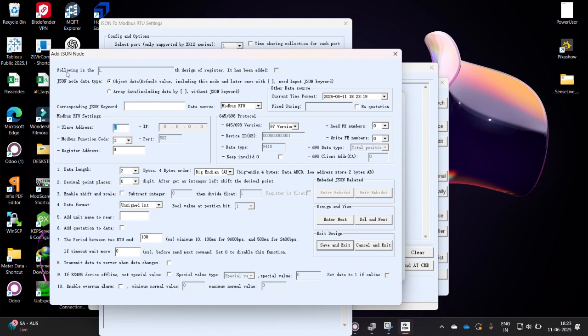After this, you can see the following is the first parameter, right? This is the number of parameters you can see. This is my first parameter, and I'm going to add the parameter I want to read from my energy meter or any water device or hardware RS485 device. This is the keyword field, the corresponding keyword, which may be anything like current, voltage, flow rate, etc. Currently I'm going to read 3 parameters, starting with kWh, so I'm putting the kWh value there.